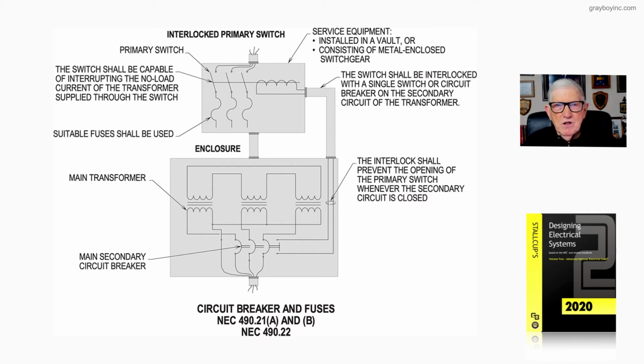Now, looking at the illustration itself, it's an interlock primary switch, just like I've read to you. And looking to the left, the primary switch, the switch should be capable of interrupting the no-load current of the transformer supplied through the switch. And then below that, suitable fuses shall be used as you see there. Now, the service equipment could be installed in a vault or consist of metal enclosed switchgear. We would select the switchgear now from Article 490, and we would go to Article 450, around 450.42, if it happened to be a vault involved.